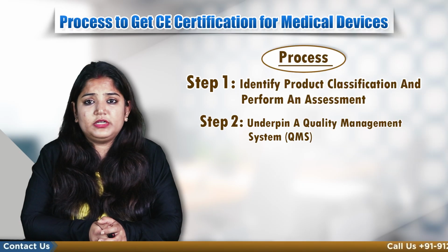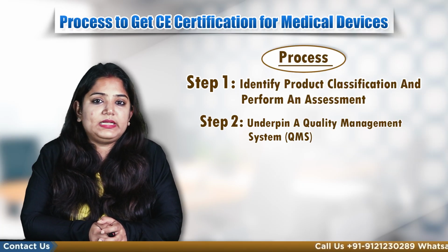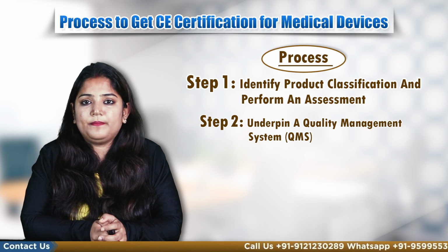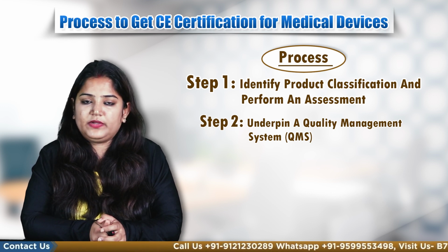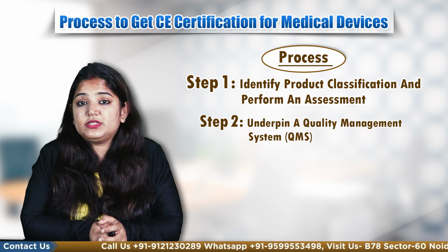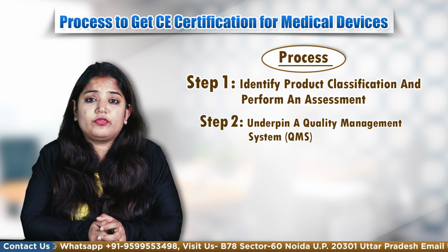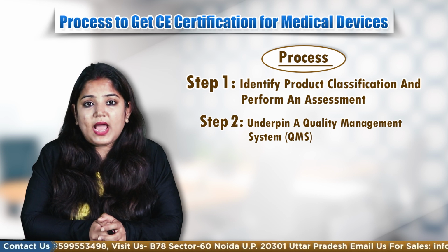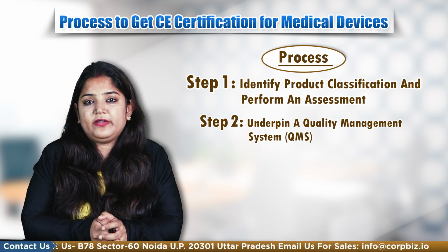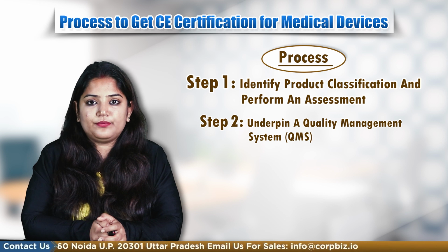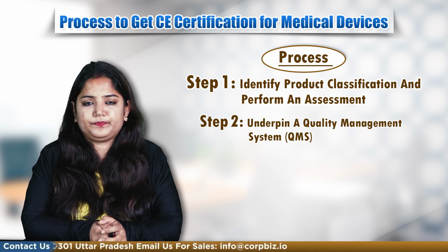There is no compulsion in MDR for medical device manufacturers to adopt ISO 13485, but it is the only legitimate standard preferred by the EU for standardization of critical processes. ISO 13485 makes risk assessment and process tracking super easy.